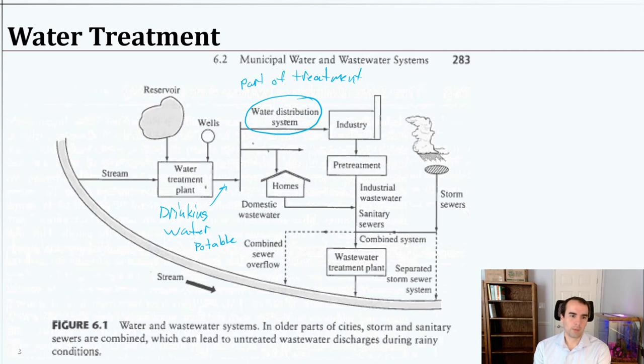Then what can happen in a flood event is we overflow the wastewater treatment, and then we have escape of combined sewer overflow. So we've got that raw sewage plus the storm sewer runoff entering our lakes and streams, and that's a health hazard for anybody around, and that's essentially taking our wastewater and directly discharging it, which is exactly the opposite of what we're designing the system for. So this is more and more being banned, and infrastructure that has been in place to combine the flows throughout the nation are slowly being separated to fix this issue.